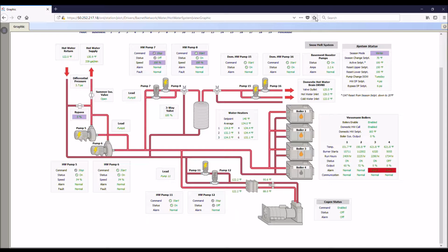And honestly, we have no idea when they're trying to run or not run. So the status point is just, well, they're running now or they aren't. The alarm point is a fault contact coming from their general controls. So if those controls ever go into alarm, that's what this alarm point is. Otherwise, for all the pumps, the alarm point is, we are commanding that point on, but we aren't getting status within 10 seconds. So then you'll see this alarm point turn into alarm. That's for all the pumps.